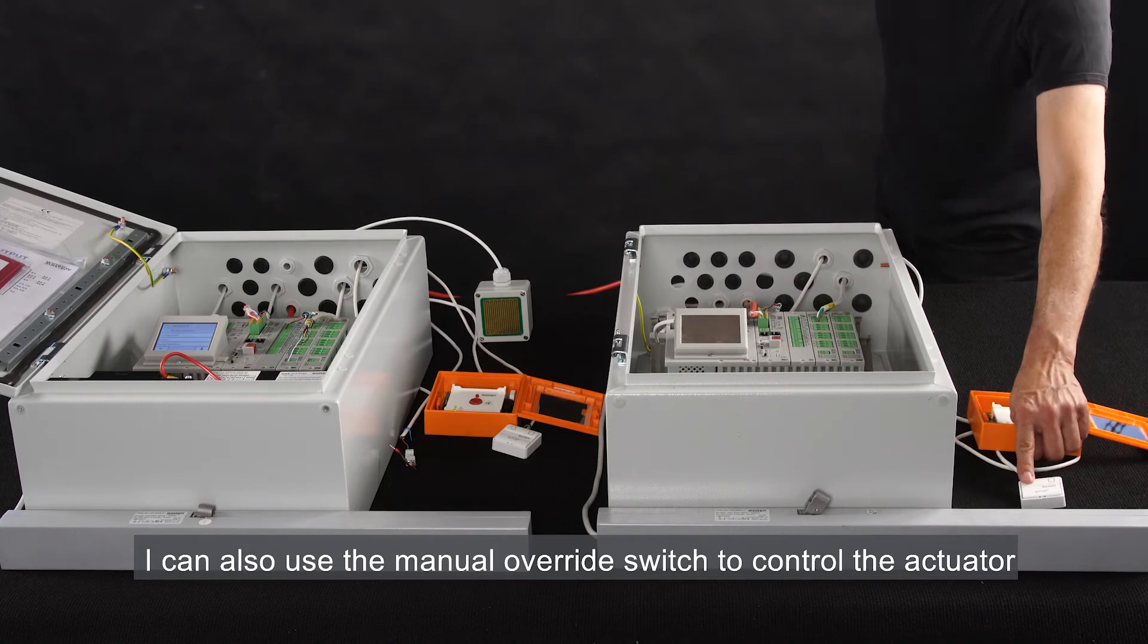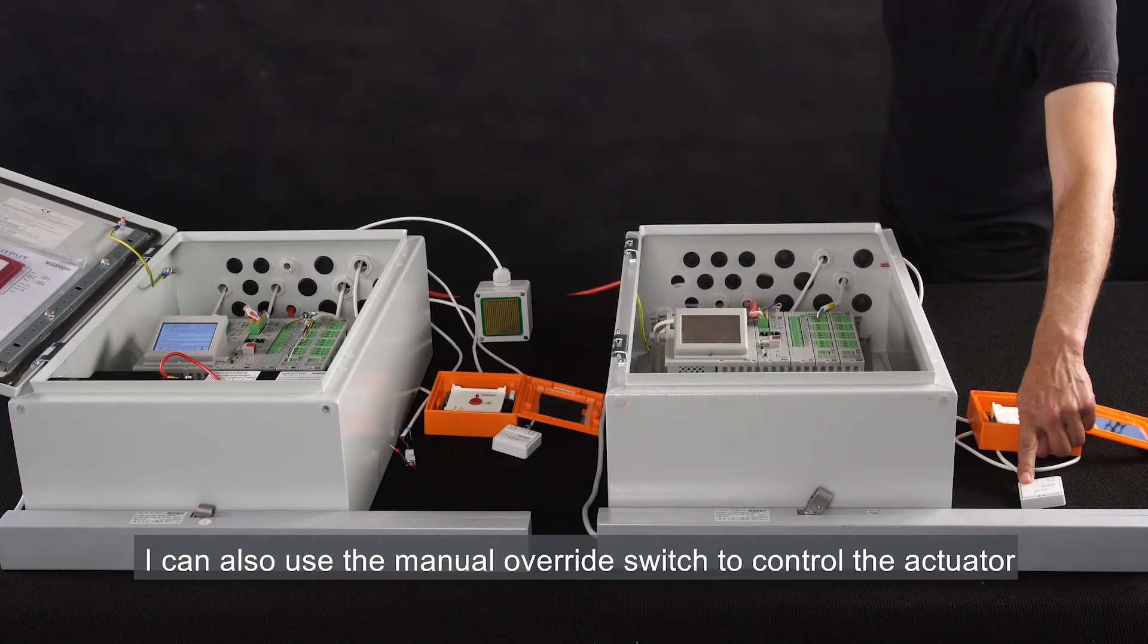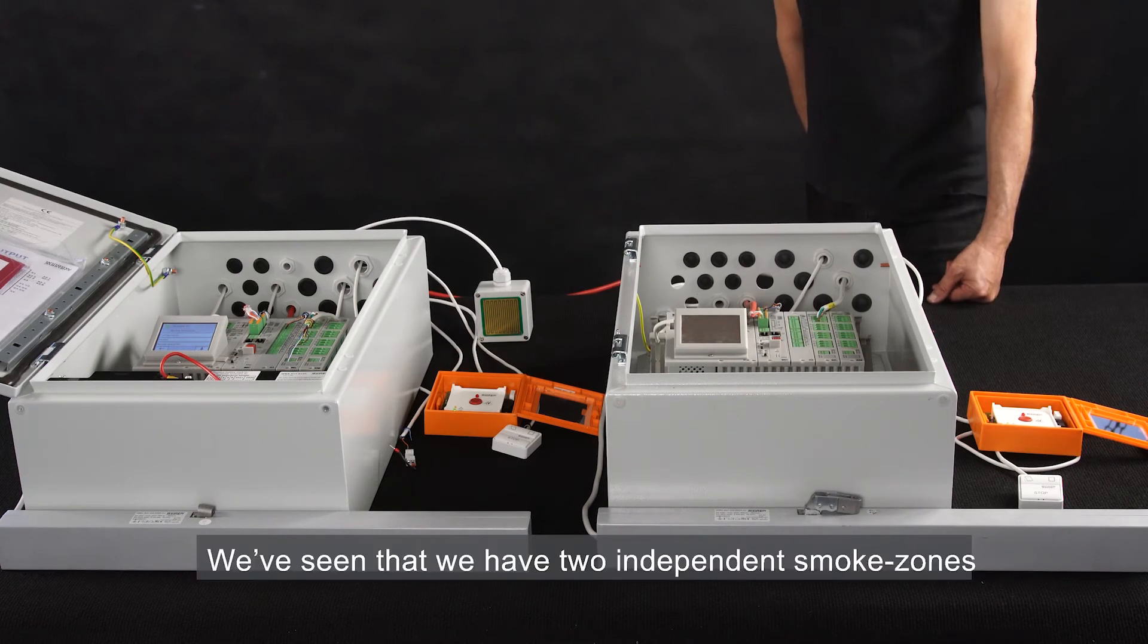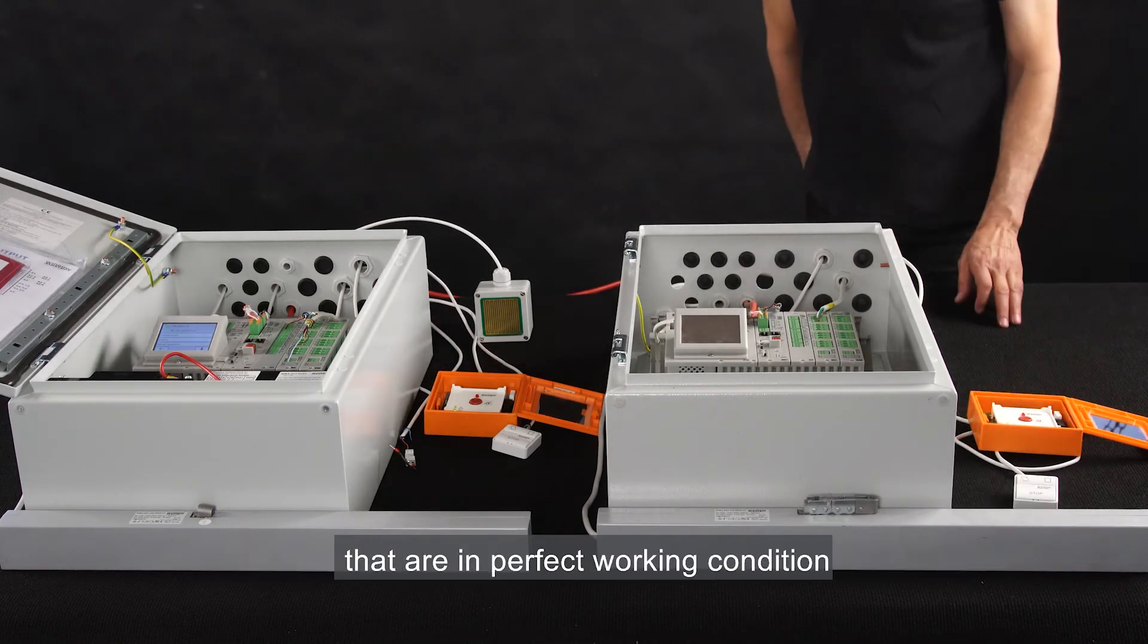I can also use the manual override switch to control the actuator. We've seen that we have two independent smoke zones that are in perfect working condition.